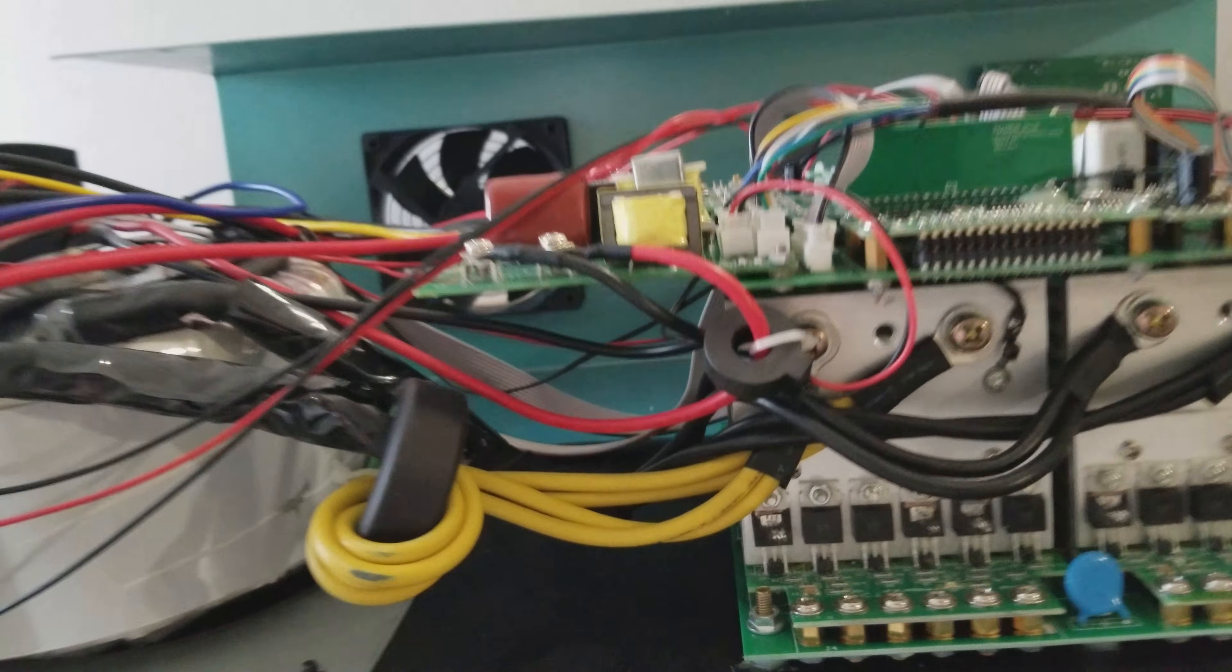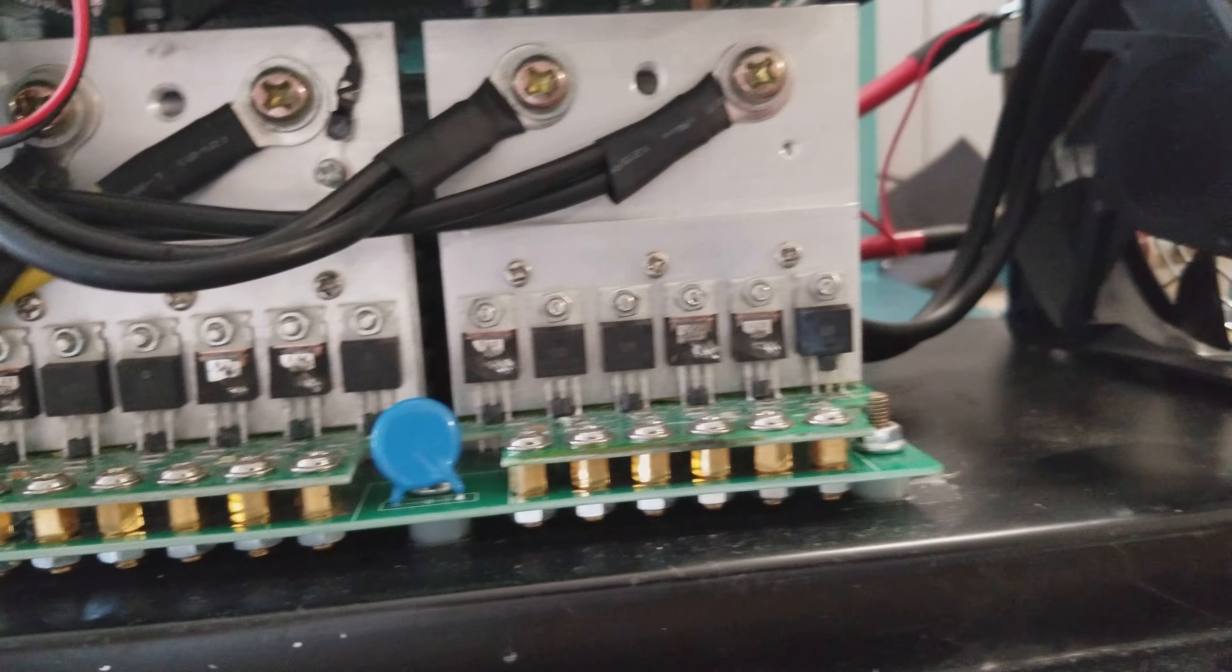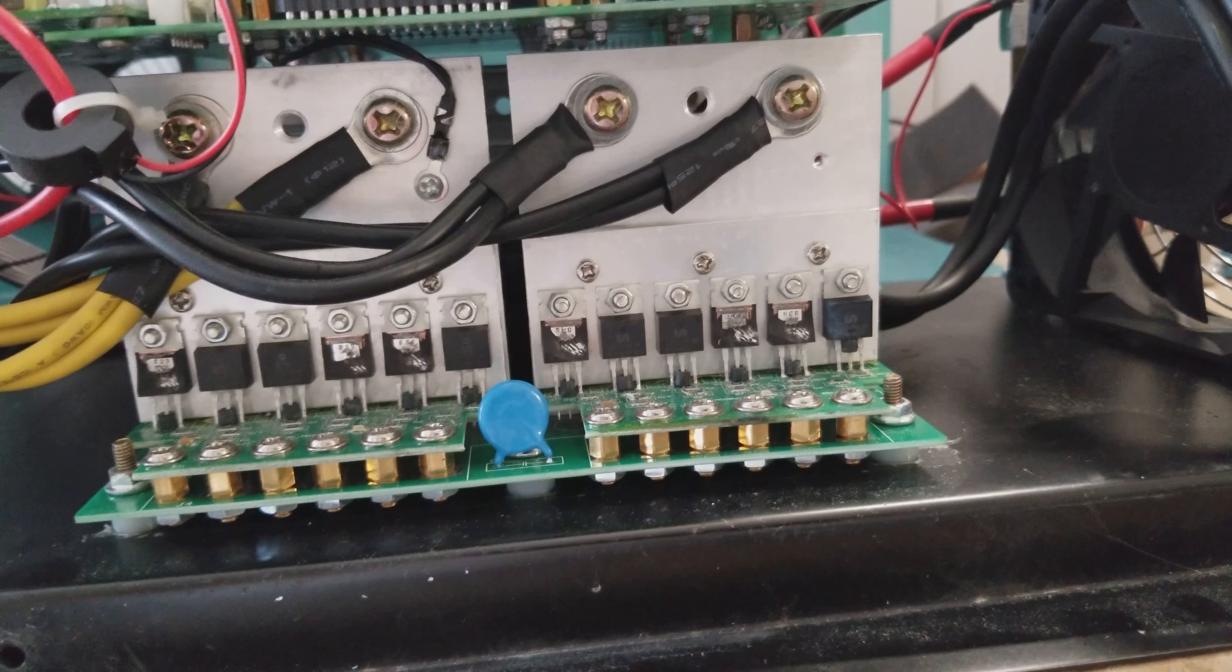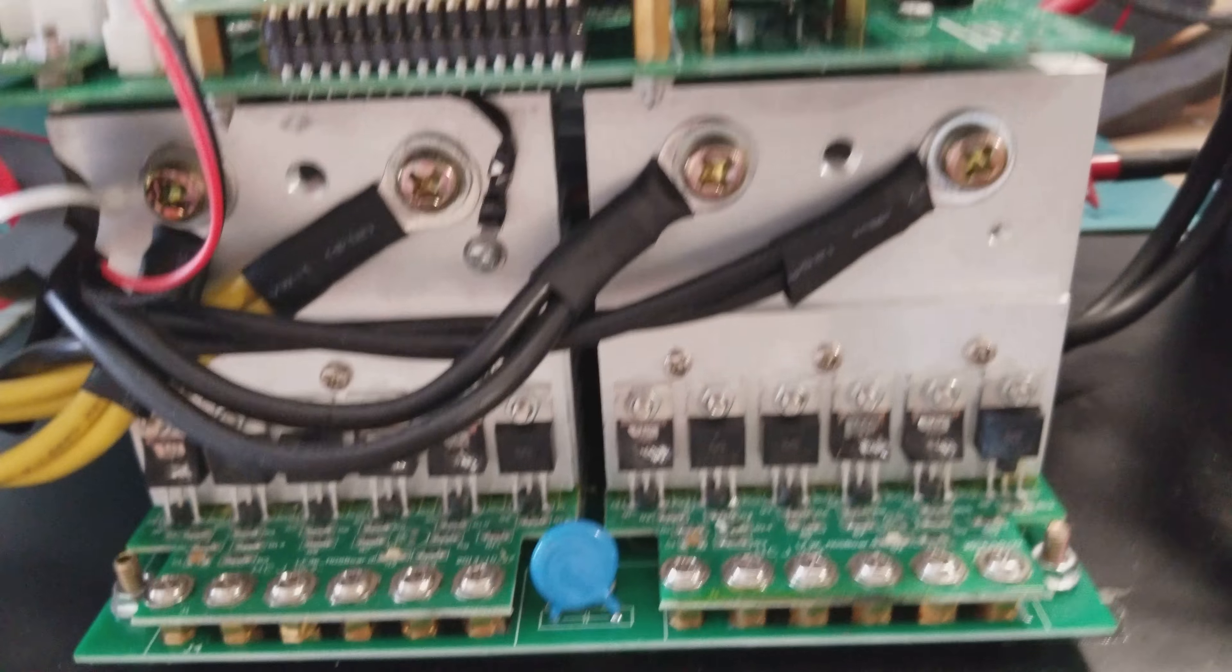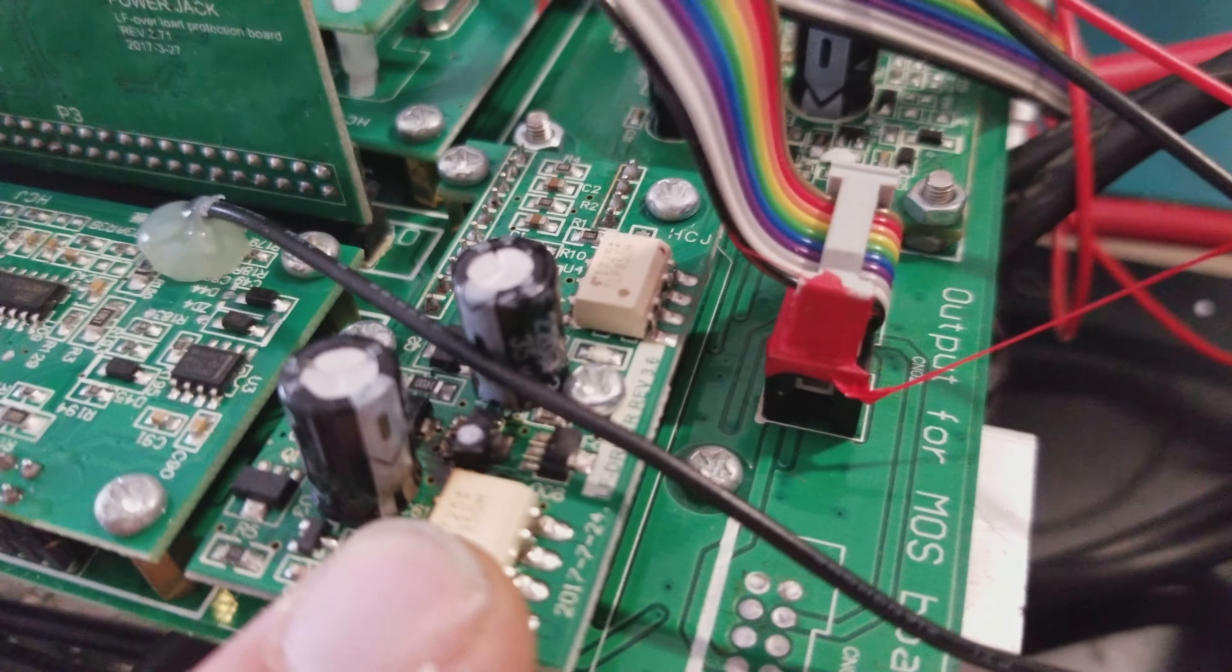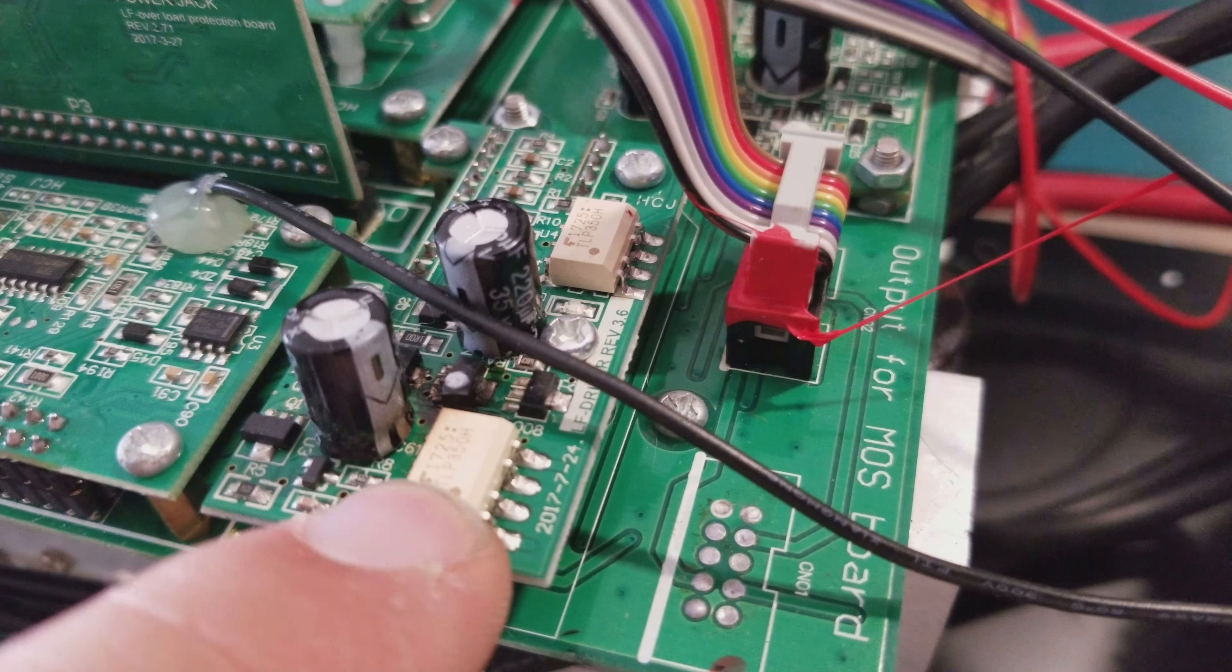So if you open it up and you see this damage here, where the MOSFET boards are damaged like that, then check the rest of the inverter to see what other damage there might be. Look for burn marks. In this particular case, you can see that the low frequency driver here was all burned up because it overloaded.